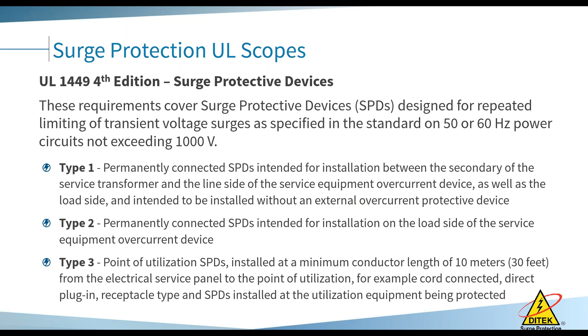So if you were to put that on your residential panel, that would be on the line side. Type 2 is going to go on the load side. That's going to be your 2-pole breaker on your residential or a 3-pole breaker on a commercial service, and you'll hook it up to one of those. Type 3 is point of utilization SPD. That's normally more than 30 feet away, and that could be something like your branch circuit coming to your fire alarm panel, or that copying machine on the other side of the building that is a $5,000 or $6,000 copying machine.